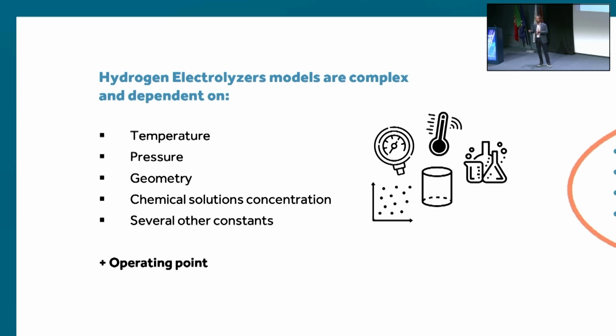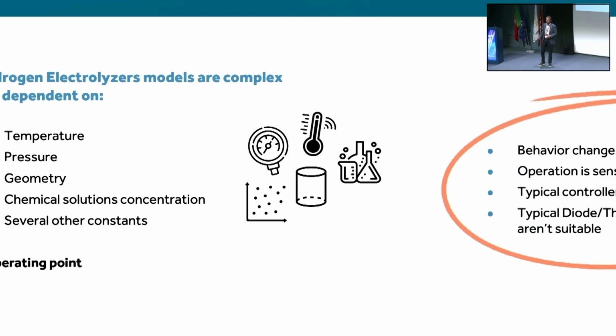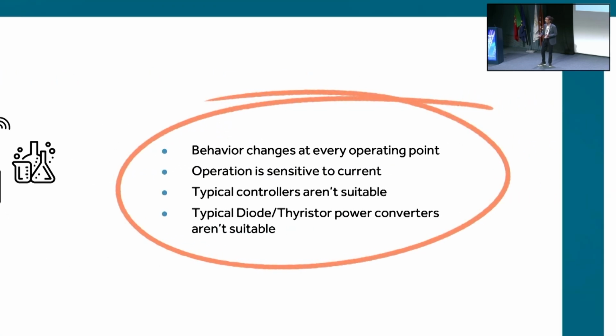When the operating point changes depending on different parameters, from the power electronics perspective we have problems, because the behavior of the electrolyzer changes at every operating point. It can be sensitive—electrolyzers are very sensitive to current. This means typical controllers used in power systems and power converters can't be used anymore, and typical power electronics interfaces like diodes and thyristors simply can't provide the grid services we need in terms of flexibility. As has been the key word of the speeches today: adaptivity.